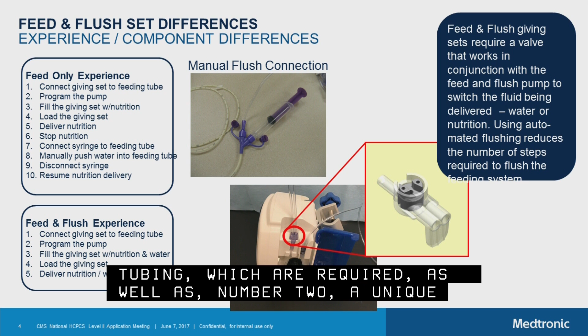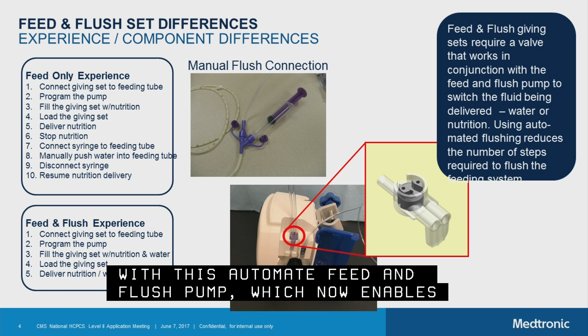An automated feed and flush system requires 2 parts. First, a feed and flush set, as well as, of course, the automated feed and flush pump. Feed and flush sets are uniquely and technologically different from feed-only sets because they have, 1, a flushing and hydration bag and tubing, which are required, as well as number 2, a unique valve that works in conjunction with this automated feed and flush pump, which now enables switching between nutrition and water infusion.